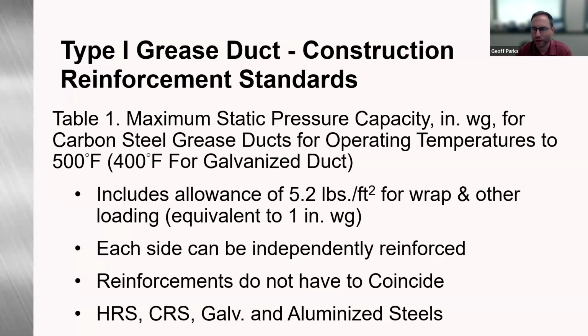So table 1, which we're going to look at here in a second, this is the maximum static pressure capacity in inches water gauge for carbon steel grease ducts operating at temperatures up to 500 degrees. So there's an allowance in this table of 5.2 pounds per square foot for wrap and other loading, which again is equivalent to 1-inch water gauge. Each side can be independently reinforced. Reinforcements do not need to coincide. And then hot rolled, cold rolled, galvanized, and aluminized steels are covered.